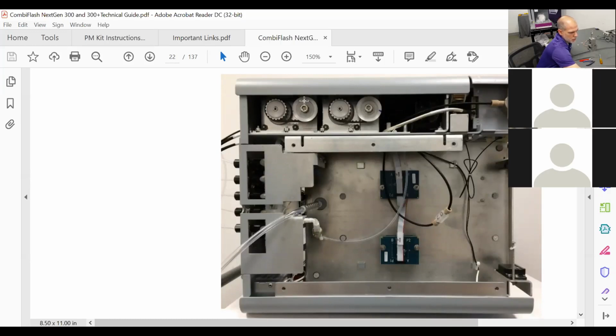So you can see the belts and the pulleys. These are the RFID readers. That's radio frequency identification. So our test tube racks have little tabs on the bottom of them that tell the unit what size they are. You can select manually, but with the RFID, you just insert it and the machine reads it and knows what you've got there. Now, if it stopped reading racks, you might have to replace one of these. I imagine some people in this training have done that before, and it's not the funnest thing to do, but it's always easier if you tip it on its side like this.